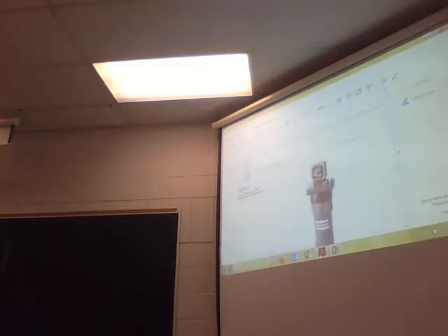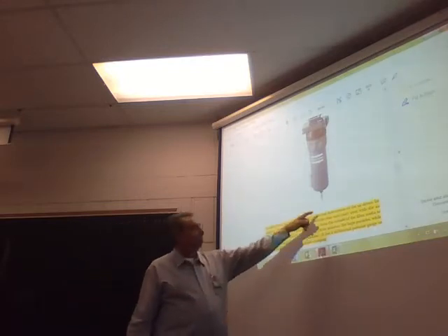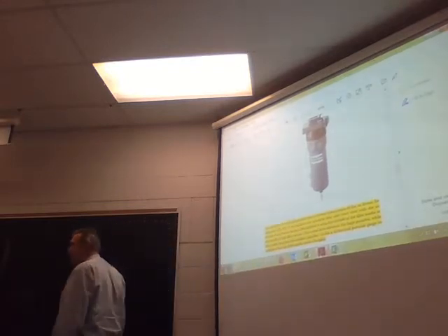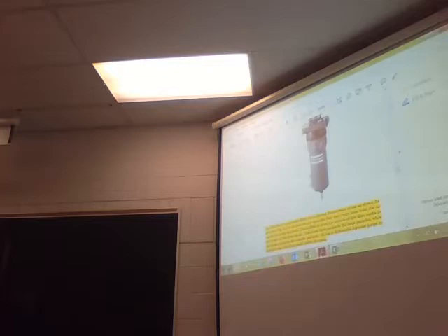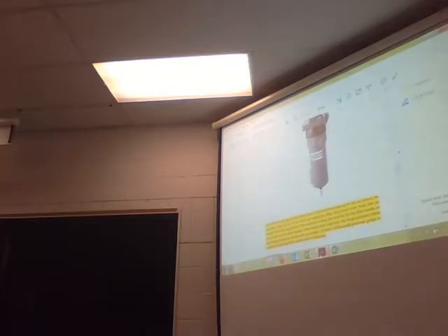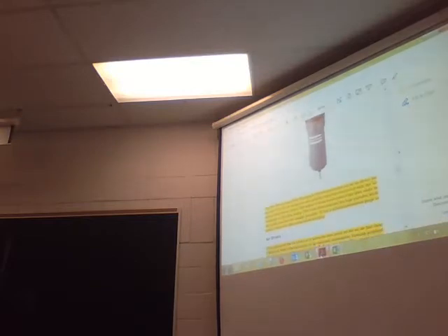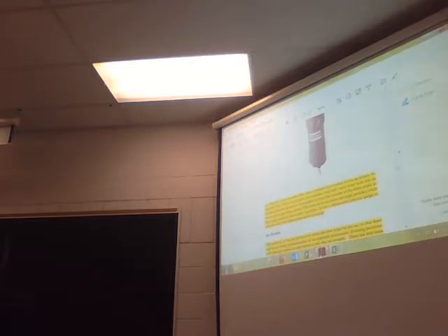So this one can either be manual or you can have a trap on the end of it. Ours were all done by hand, as part of your rounds, mostly because that way I knew you had to get out of the office and go check the plant. So these would be around different locations: after a reducing station, maybe before the dryer, one after the dryer, by the receivers. All of these had to be done.